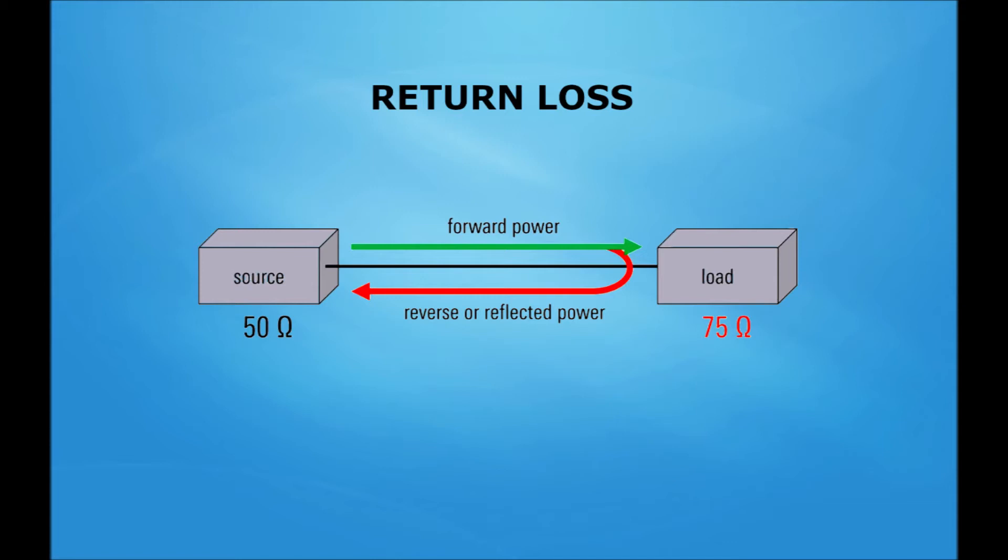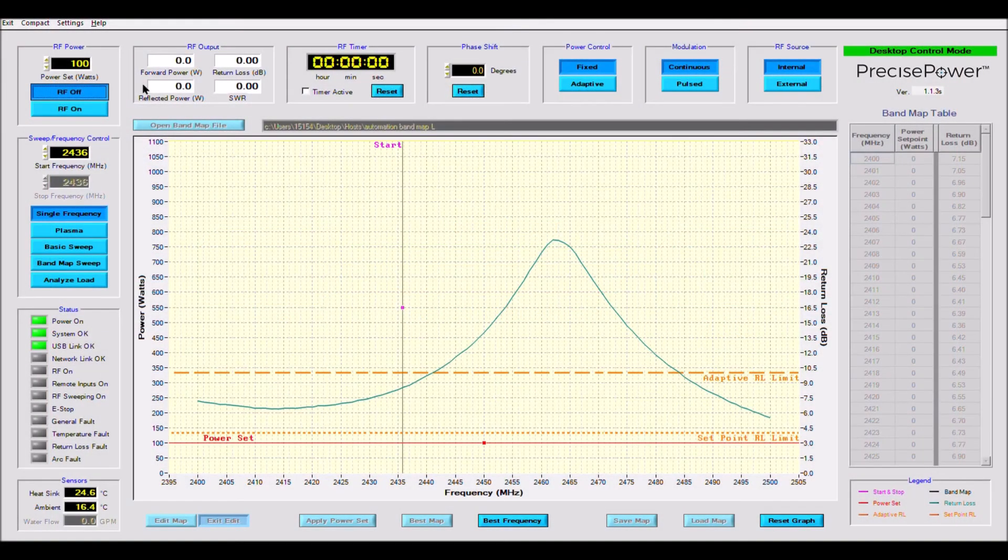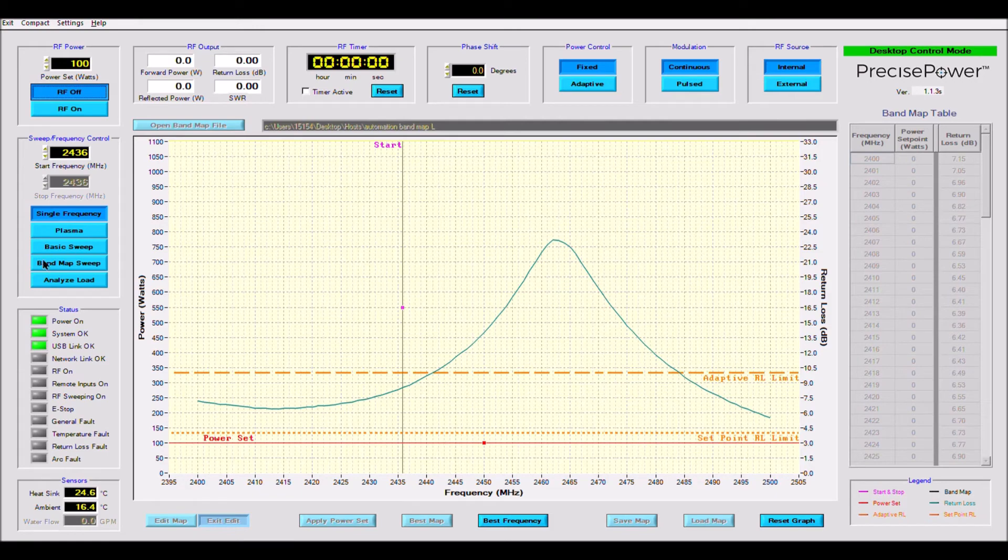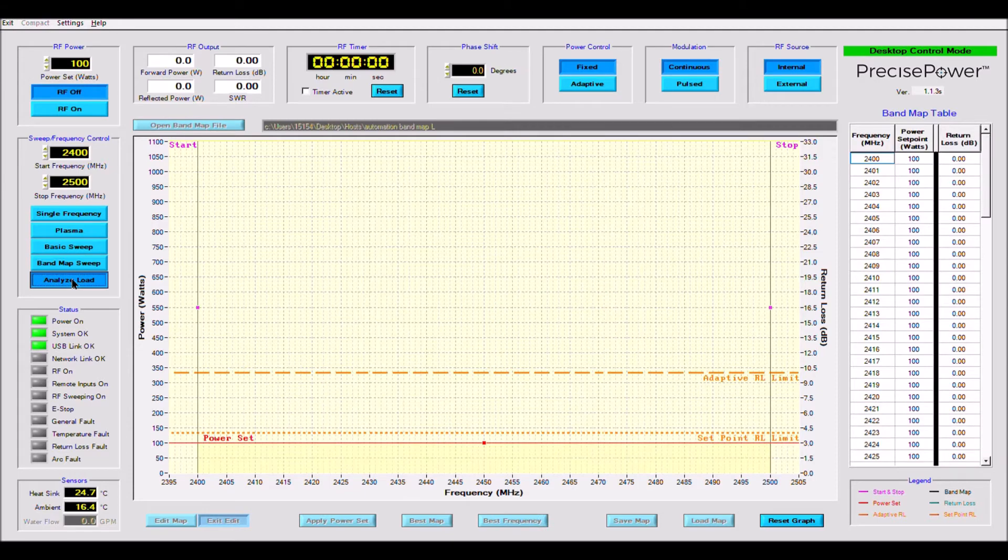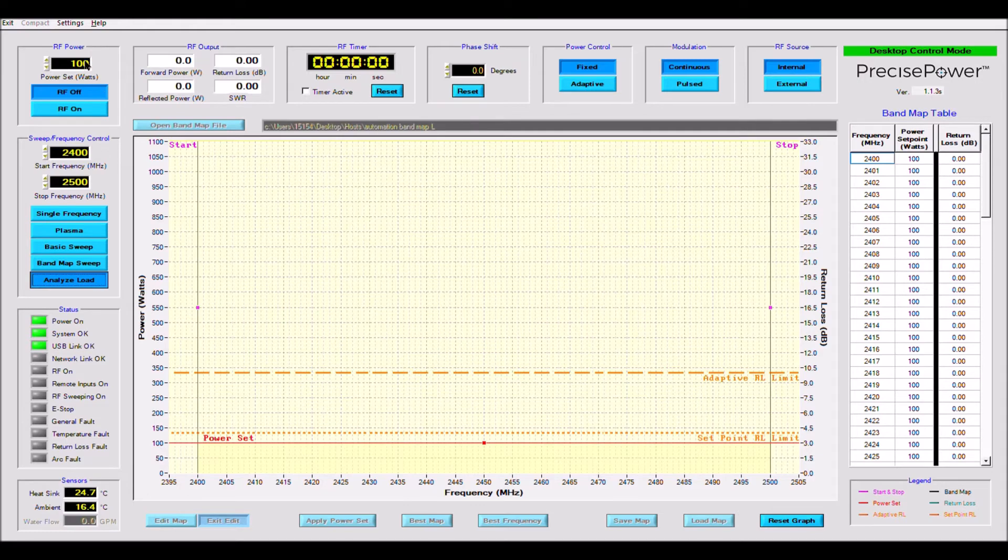Now back to the demo. First, I am going to click on the Analyze Load Mode. This mode performs one quick sweep across the band and plots the return loss at each frequency. The sweep will start at 2.4 GHz and end at 2.5 GHz at 100 watts. Now I click on the RF on button and it will run one time then turn off.